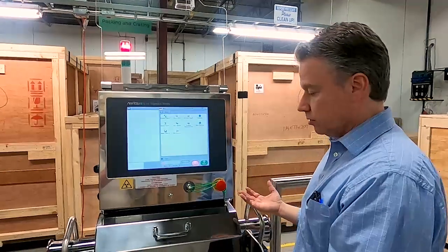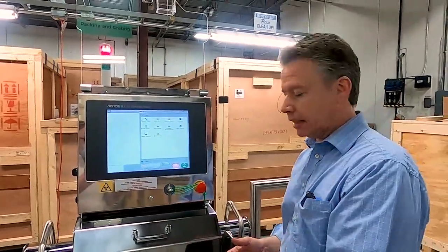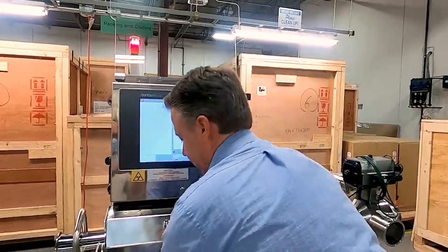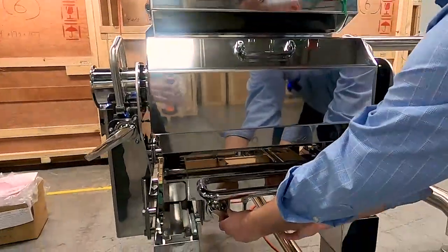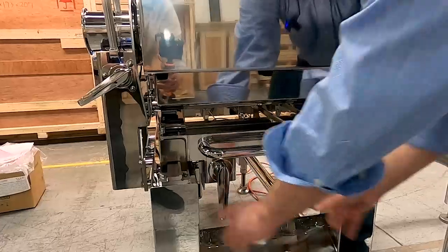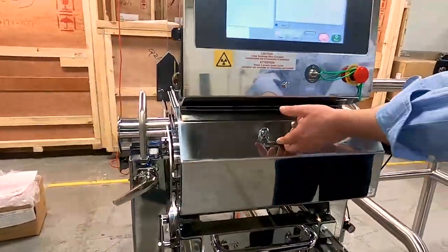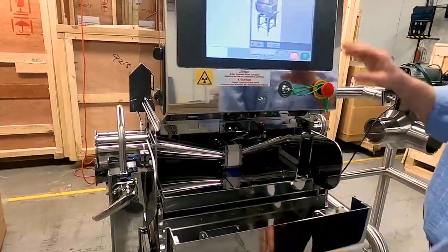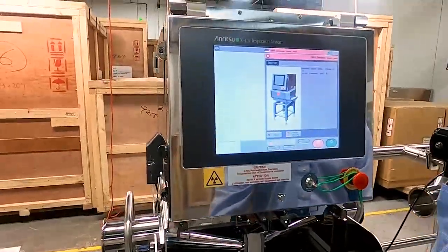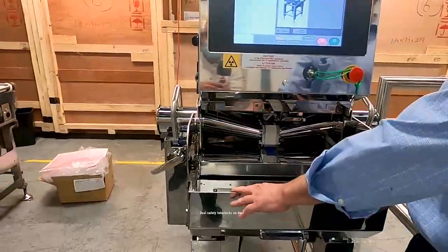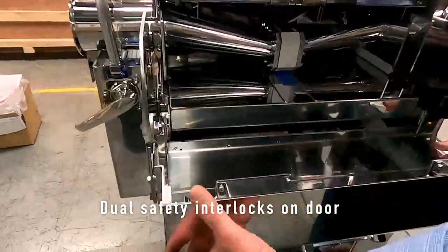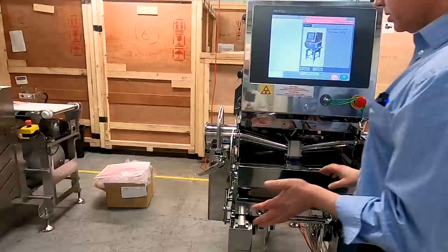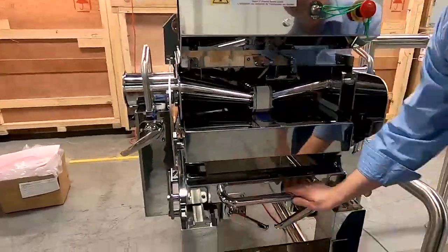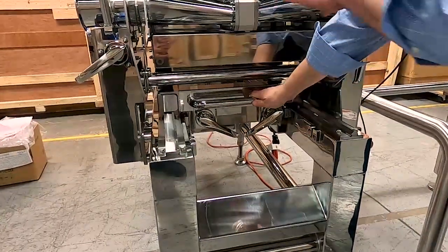Another nice feature of this machine is everything will come apart without any tools. So we're going to show you how to pull the system apart for cleaning, and we'll show you what this manifold actually looks like. So I'll slide it back out to the front, or the run position. And I'm going to open the door. You'll see that I'm going to break the safety circuit. So it's going to tell me the door is open, but now I can pull the door right off. And you'll notice as well there are two interlocks on the door. So pull that off, and I'm going to slide it into that calibration position. So that's going to give me better access to the manifold.